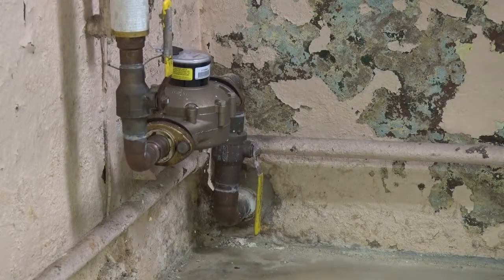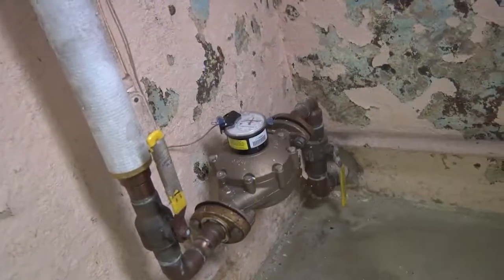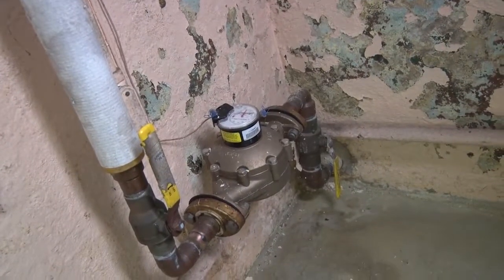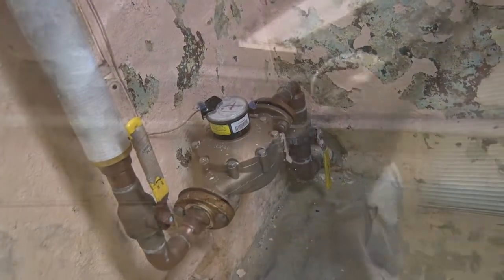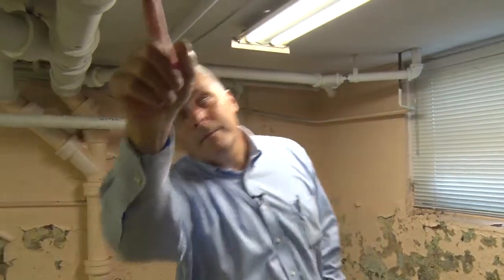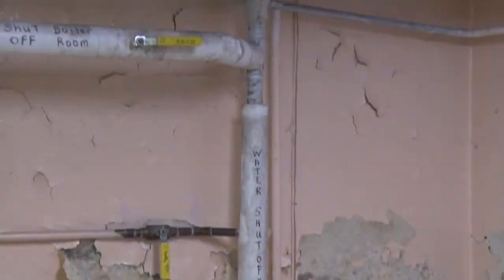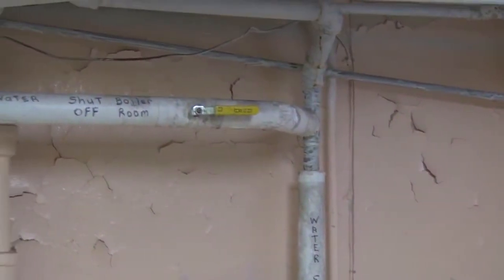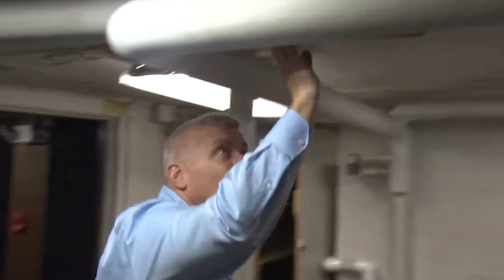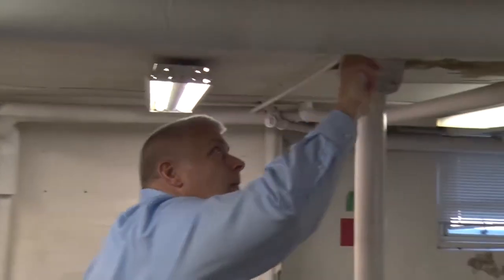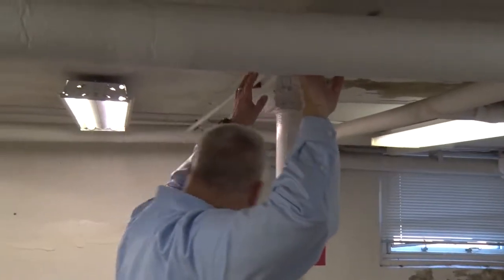For the plumbing profile, the walkthrough would allow you to locate and verify the point of entry, which is where the service line enters the building, the material of the service line, and the material of the internal potable plumbing, such as lead pipes, lead solder, brass valves, fittings, or fixtures, storage tanks, and point of entry treatment. The following video clip is from a plumbing profile walkthrough.